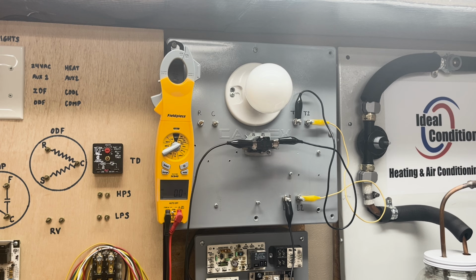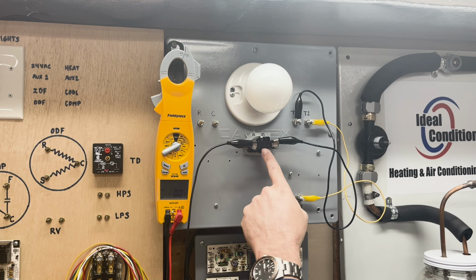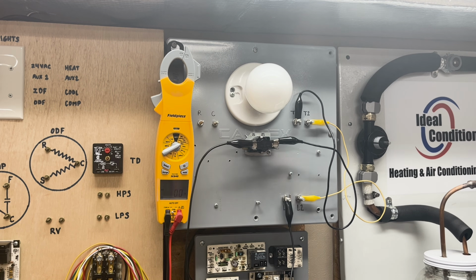You may experience your heat strips running, and if you're trying to cool with that, you're not going to get a good temperature split across your air handler, not just your evap coil, but the entire air handler. As you remove 20 degrees of heat going across your coil, you'll warm that air back up about 10 or 15 degrees, and you'll see like a 7, 8, or 10 degree split on your air handler.